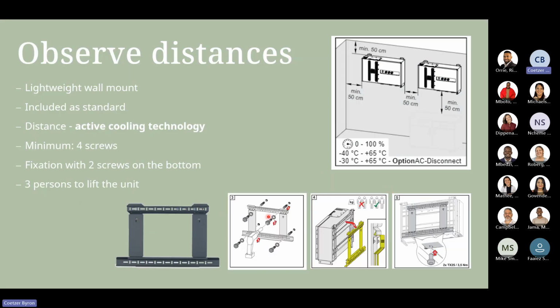So with the device, you will get your lightweight wall mount available in the box. This will allow you to mount to the wall directly. You will have to keep in mind the distance between the units, as it is 50 centimeters between each unit, as well as the safety clearance from the top of the unit and from a wall edge. This is because if you remove the covers and need to remove a power stack, we need that 50 centimeters in order to remove the power stacks correctly out of the unit itself.